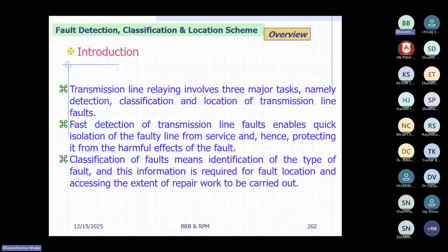and then the lineman can see that there is a fault and some maintenance needs to be carried out. What is the first task of the utility person? The first task is that he or she has to operate the auto reclosers. And if he has to operate auto reclosers, there is a debatable issue: whether I have to reclose the circuit breaker pole once only, twice only, or thrice only. Let's say there is a fault, I open the breaker and then I reclose it. Still there is a fault. Again my breaker becomes open and remains in open condition. This type of situation is known as instantaneous trip lockout. After one reclosing operation, it remains in open condition.